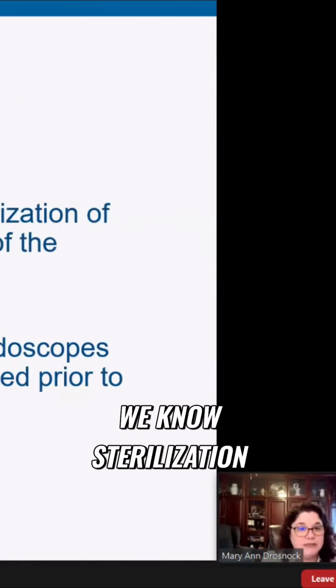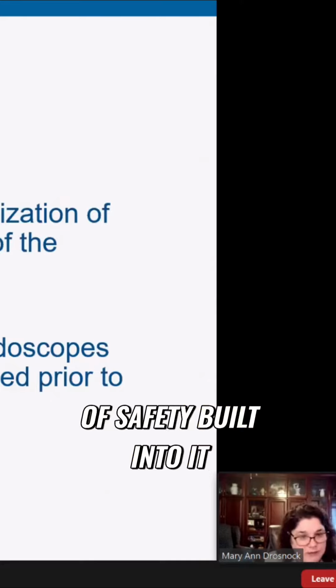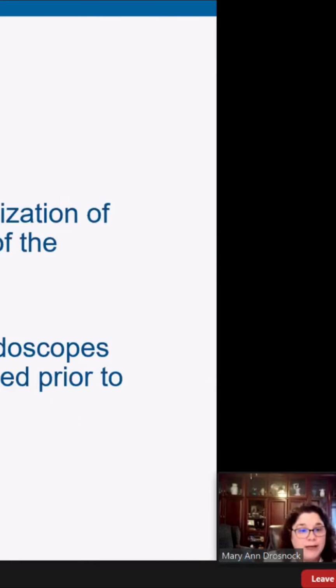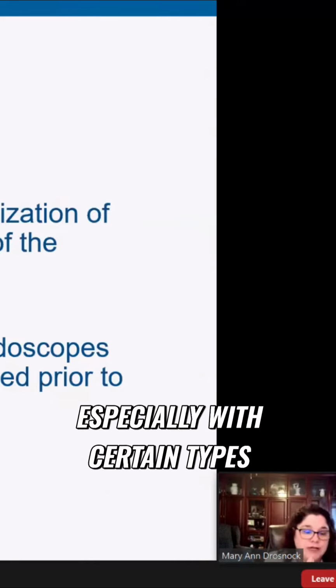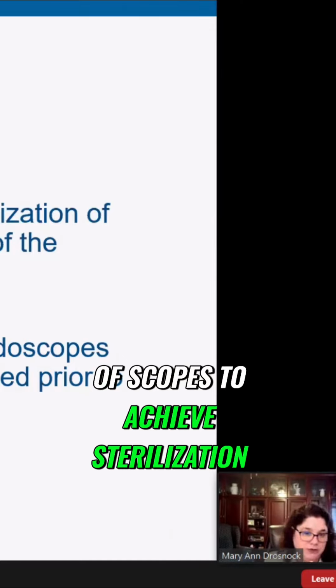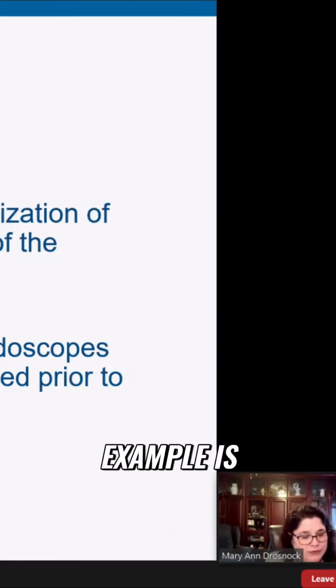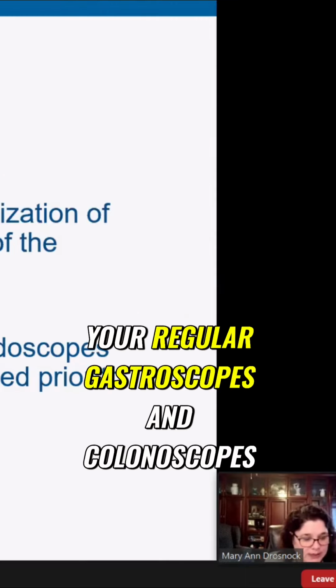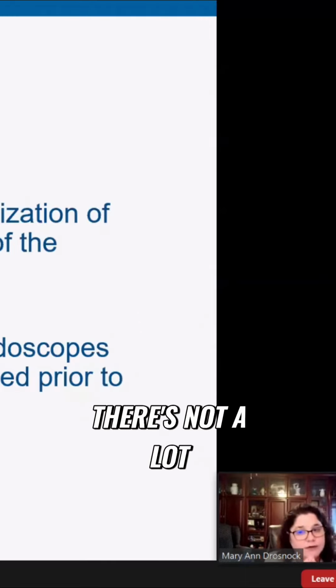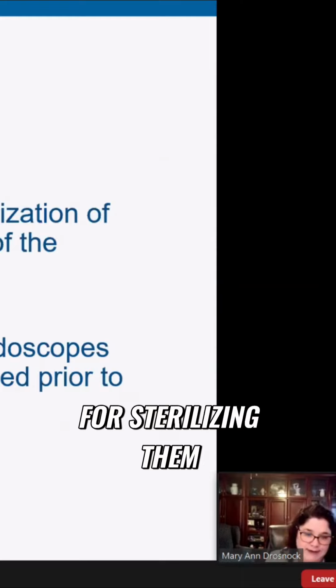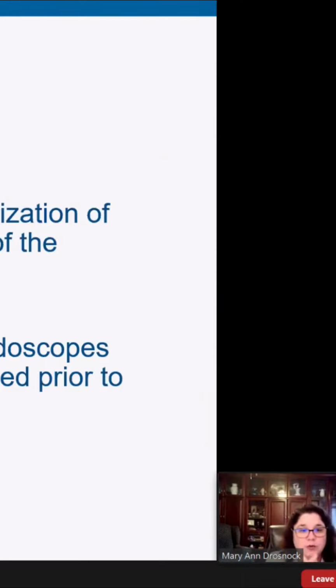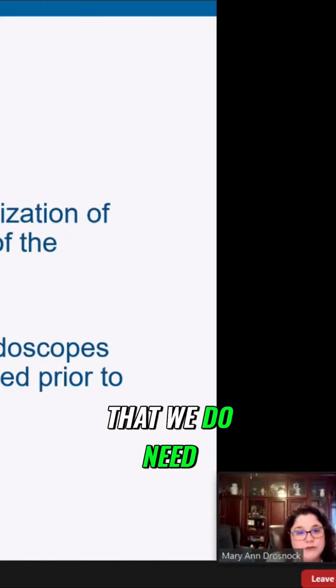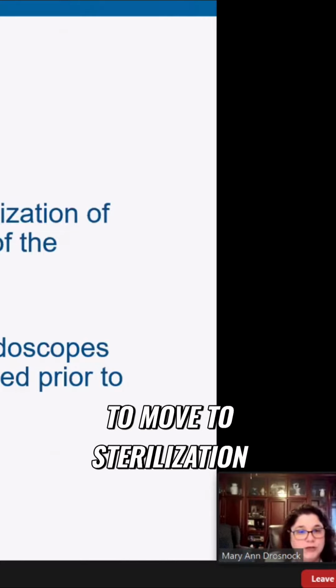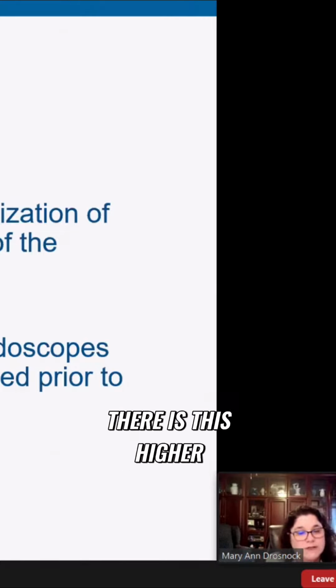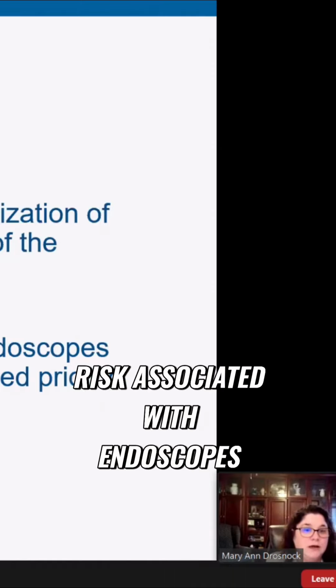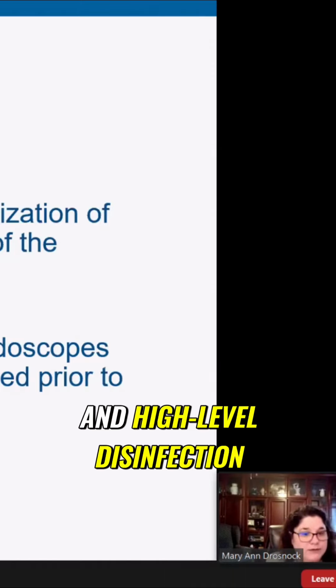Okay, so we know sterilization has a higher margin of safety built into it, but it is difficult, especially with certain types of scopes, to achieve sterilization. Example is your GI endoscopes, your regular gastroscopes and colonoscopes. There's not a lot of methods available for sterilizing them. But as a group, we felt, as Garland said earlier, that we do need to move to sterilization over the next few years because there is this higher risk associated with endoscopes and high-level disinfection.